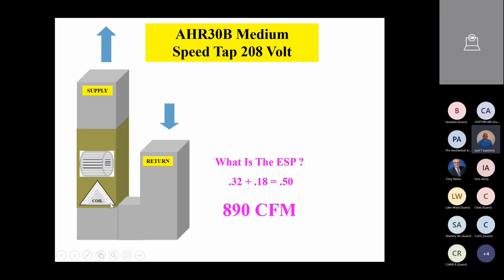And so that's an alternate to what we call a straight static pressure probe, but it's not quite as accurate as the one on the tool itself, because it's got the little holes on the side and all that. But if you get in a situation like that, just take a little 1/4 inch piece of copper tubing, or a 3/16 inch piece of copper tubing, a straight probe, drill a hole right here in the cabinet below the coil, but between the coil and the filter, and sneak that in so it's just about in the middle of that coil, so that you're reading the optimal air going through that coil, sucking across the filter through the coil, because it's really important on an air handler that the coil is included on that chart.